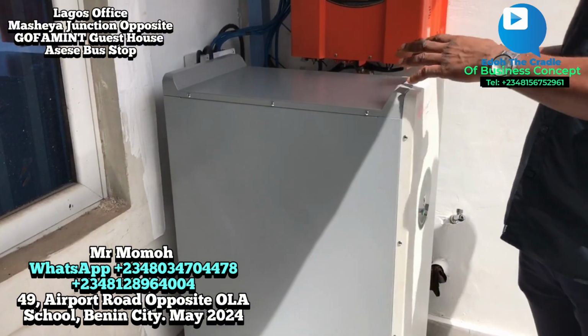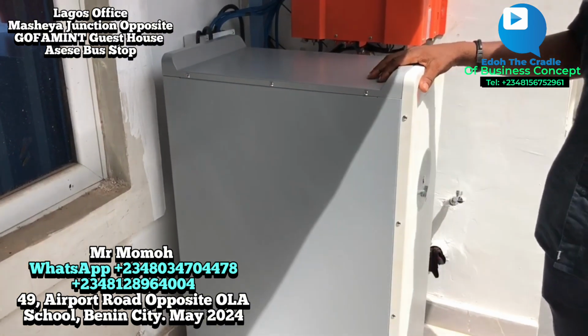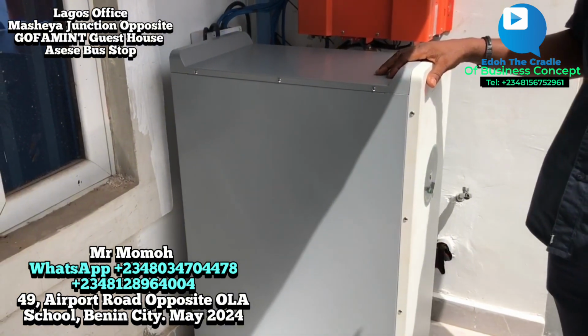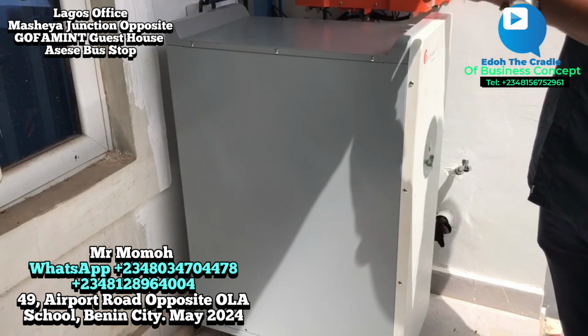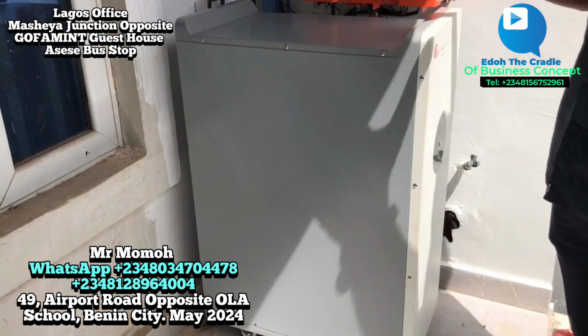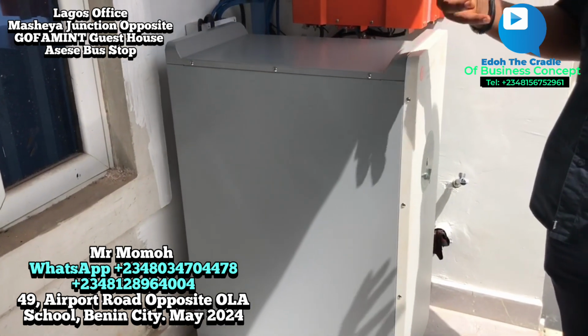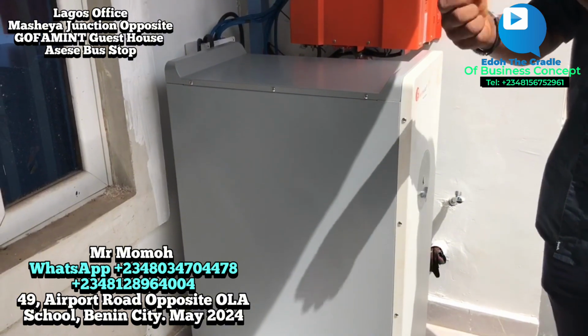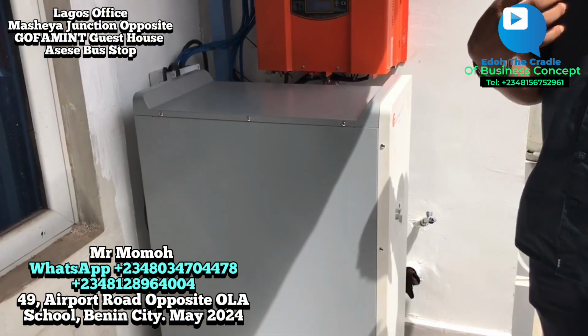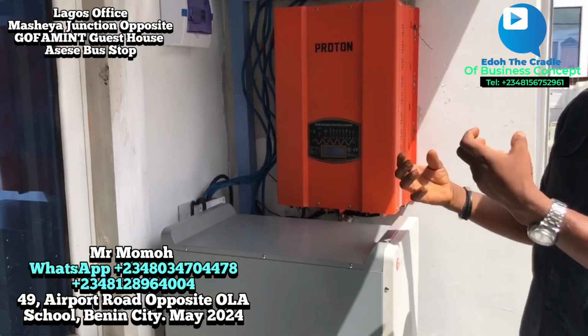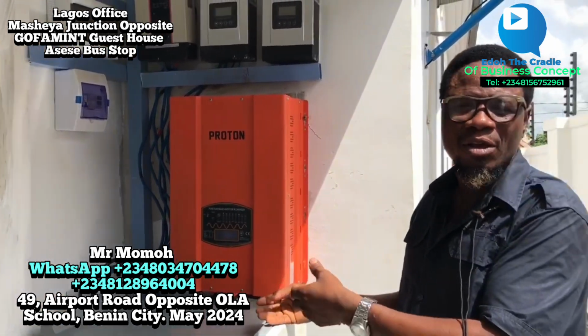You know, people think that because it is lithium, it can carry more load. No. In most cases, people get it wrong, thinking that because it is lithium, it will carry more load. No, because the kilowatts is the power rating, the storage. Lithium is calculated in kilowatts, while the other one is calculated in amps.